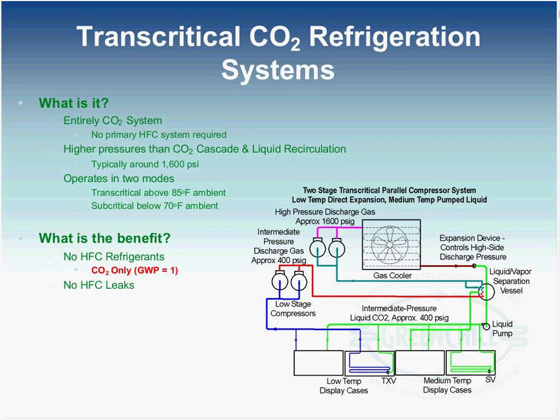Transcritical systems are known to operate in two modes. It depends on what kind of temperature you're condensing at, or if you actually do condense. One is a transcritical mode, and again, I'll show you what that looks like on a curve in just a moment, but that's temperatures above 85 degrees ambient. And subcritical mode, which would be below 70 degrees ambient. But Scott and Dustin talked about the subcritical operation of CO2, and again, that's lower pressures and a secondary or cascade arrangement. A benefit you see from this type of system is there are no HFCs. You don't have to worry about the impact of the carbon dioxide on the environment if it's leaked. Although these systems can leak just like any other system, and now you have multiple connections and things of that nature, the impact on the environment is negligible. Now, the picture that I'm showing on the bottom right-hand side is a two-stage transcritical system.